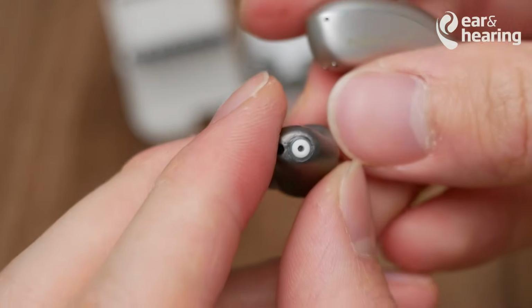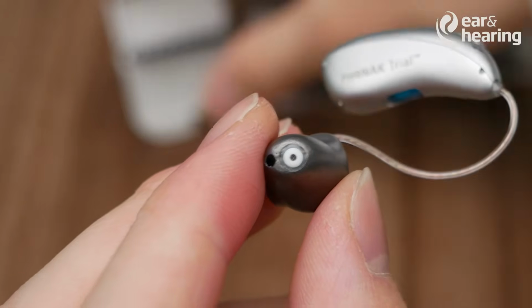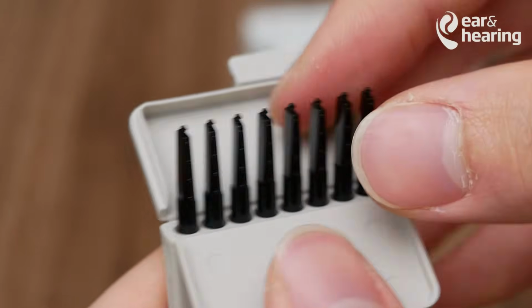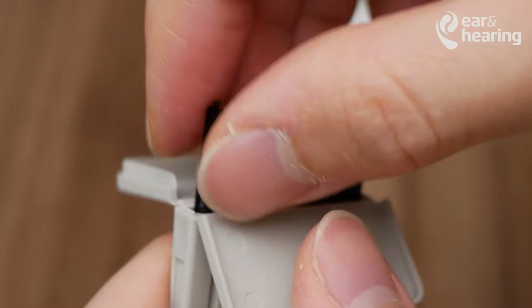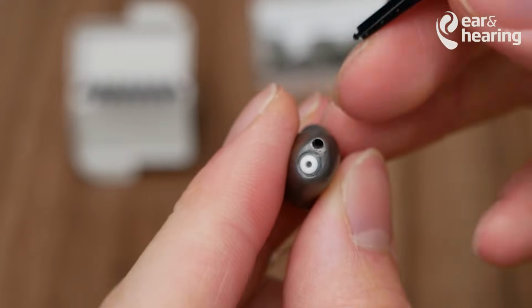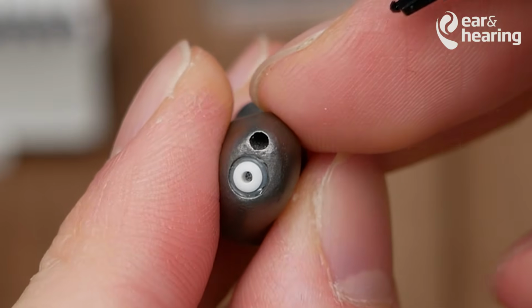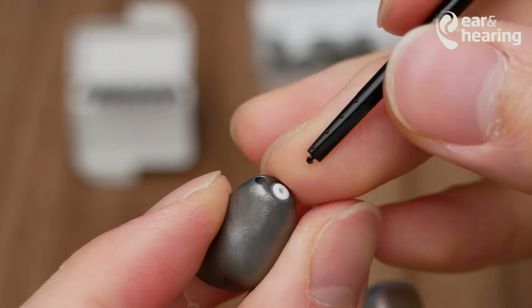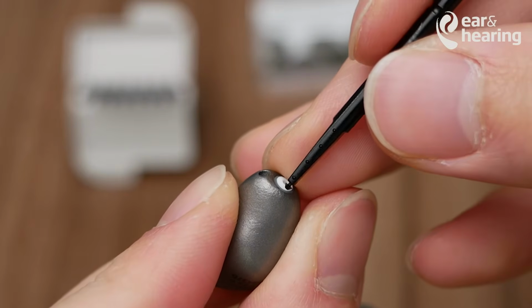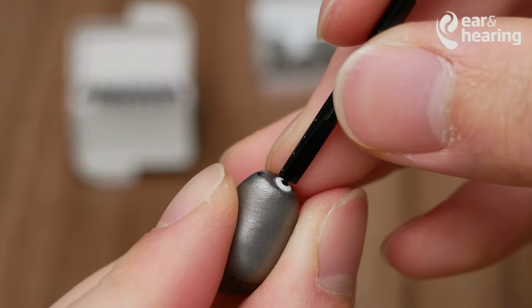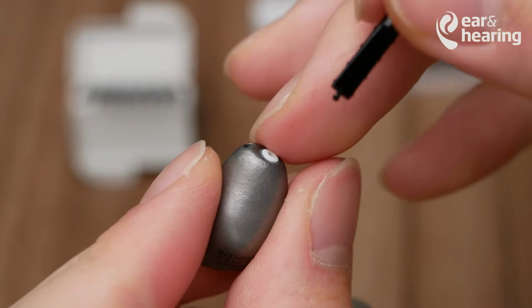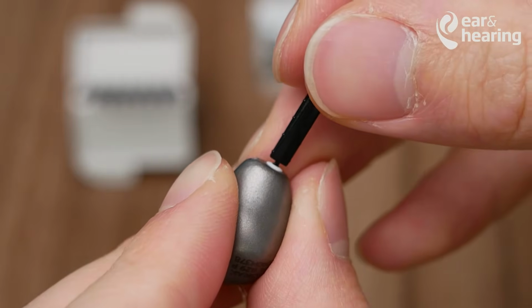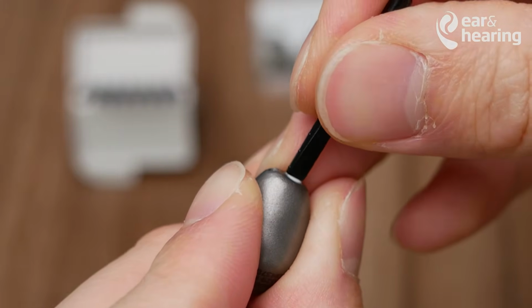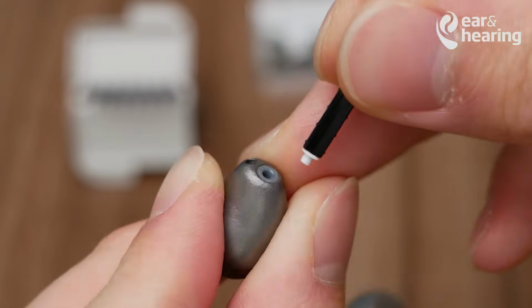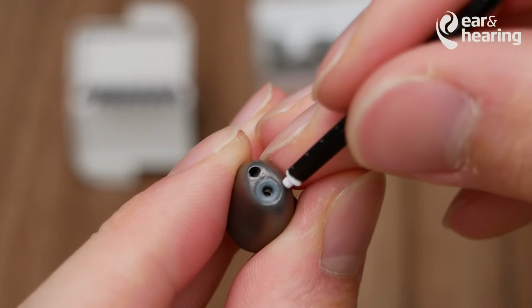Moving on, if you have an older hearing aid or hearing aid mold, you will have to use one of these CeruStops. And with the CeruStops, they come in a pack of 8. You want to be pulling one of them out. Be sure not to be too rough, otherwise they can fly off. And you want to be taking a good look at the orientation of your filter. With these, you want to be making sure that you don't twist or turn. If you do twist or turn, it can damage the filter holder and you will have to replace this whole assembly. So with this, you want to be pushing it in straight, pulling it out straight. You can see that now it's empty. There's no white filter in there anymore.